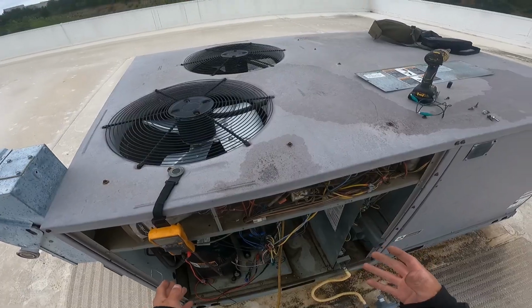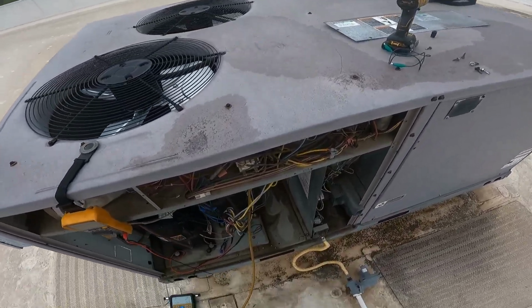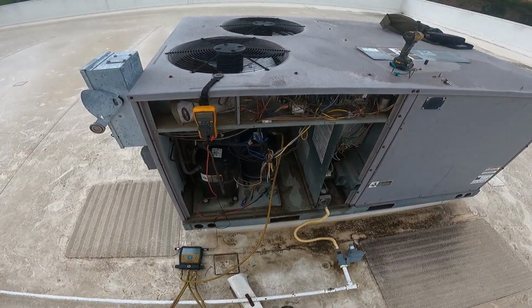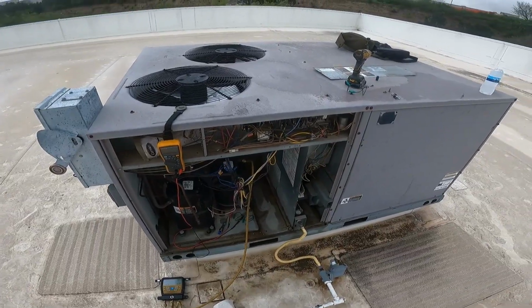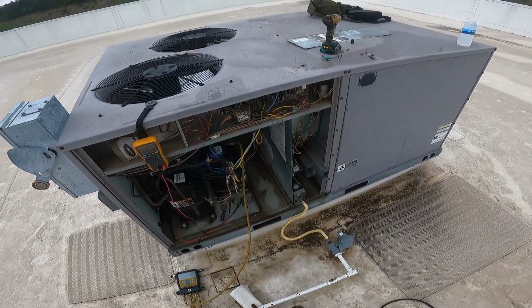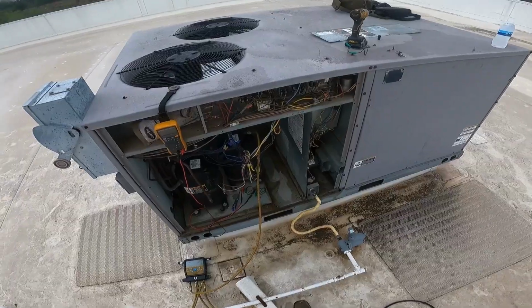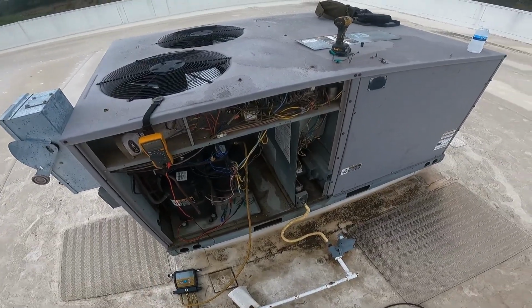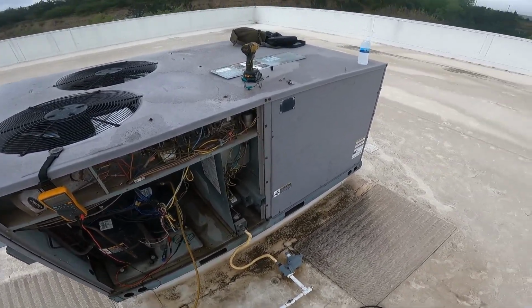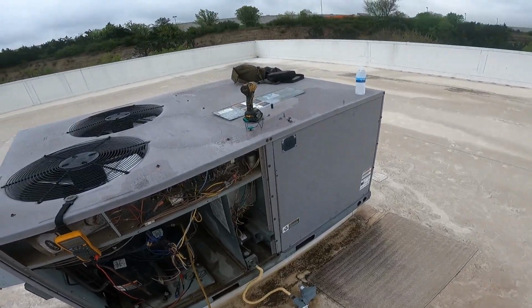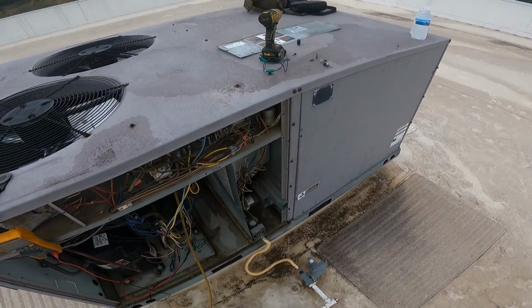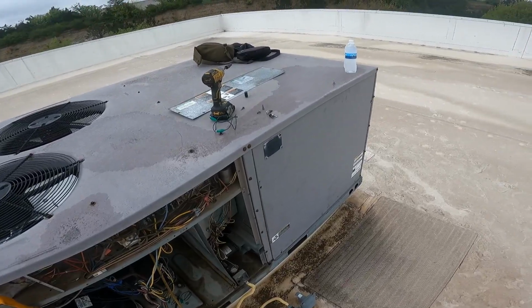I can't run this other circuit with a kinked suction line. It's not as bad as a kinked discharge line, but it's still a restriction. It's going to put a little extra pressure on that compressor. The expansion valve is probably not going to run right because it's not sucking the right amount of refrigerant into the compressor.